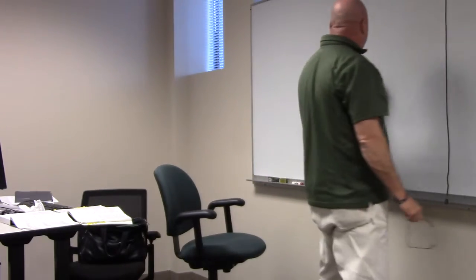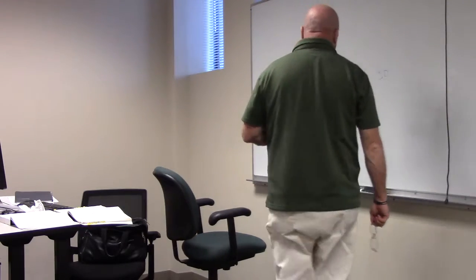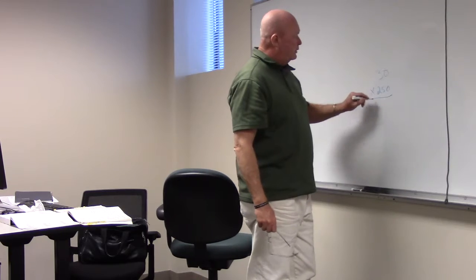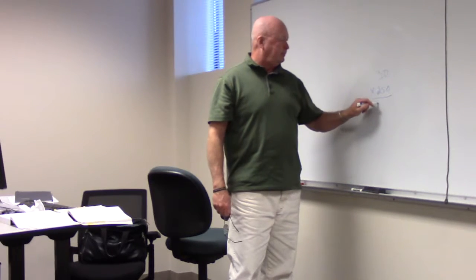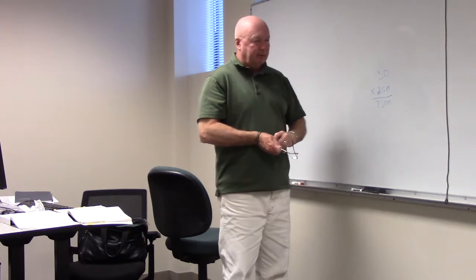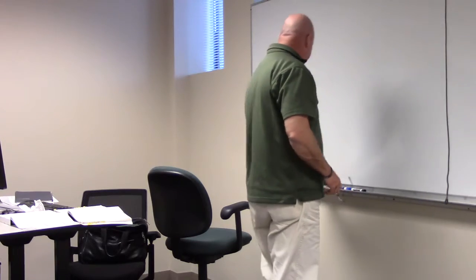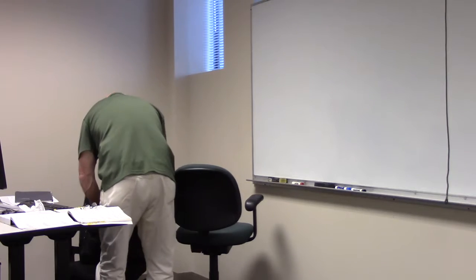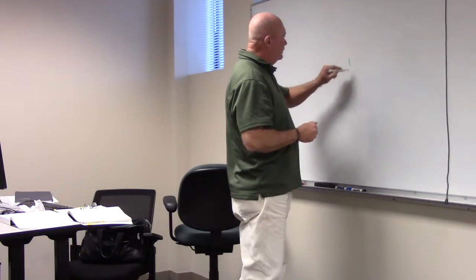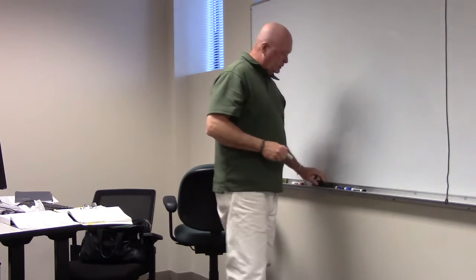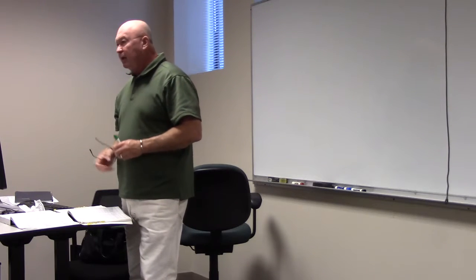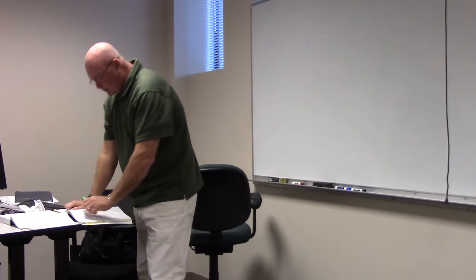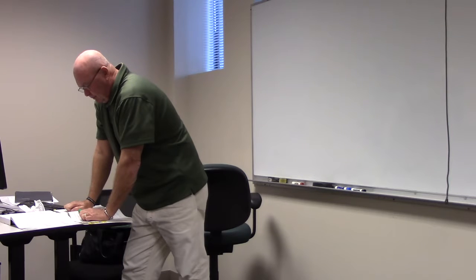So really, all we got to do here is we got 30 fixtures. It tells us to do what? Take the 30 fixtures and multiply it times the volt amps, which we already have, was 250, right? Yes. The 30 times 250 is what? 7,500. Yeah, 7,500. I'm gonna see if I can find a little bit better marker. Do this a little better. Yeah, it's a little better. All righty. Sign and outline, 600.6. We said earlier that a sign is how much? 1,200 VA. Okay, 1,200 VA.